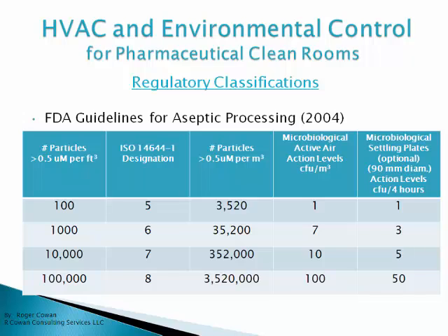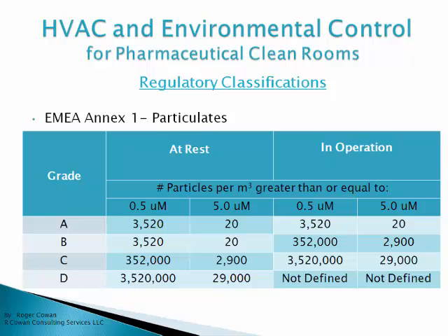ISO class 5 also has an optional microbiological settling plate specification: a 90-millimeter settling plate exposed for four hours has a limit of not more than 1 CFU per plate. You can see the other classifications as well. Over in Europe, EMEA Annex 1 has a separate set of specifications for particulates, classifying rooms as grade A, B, C and D.